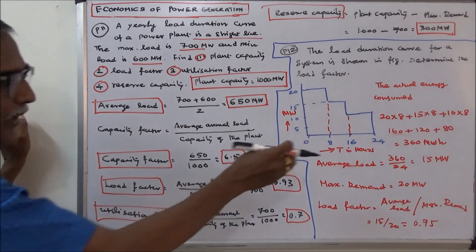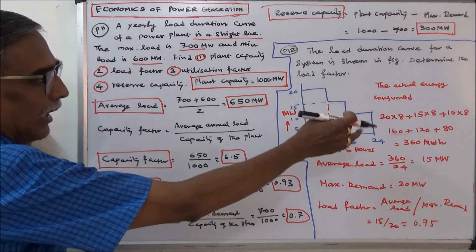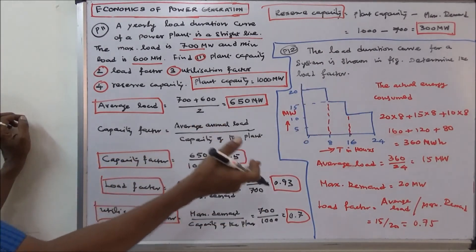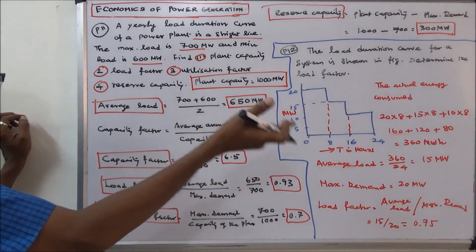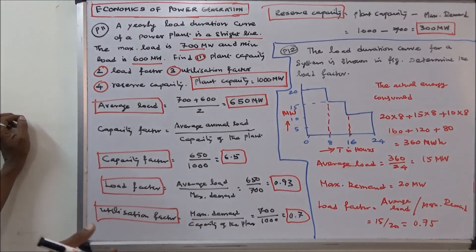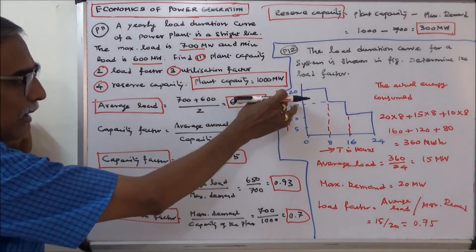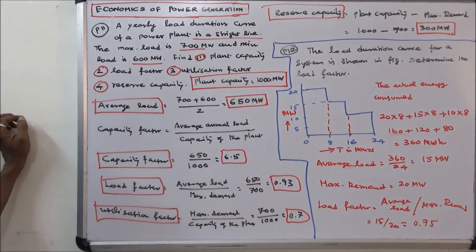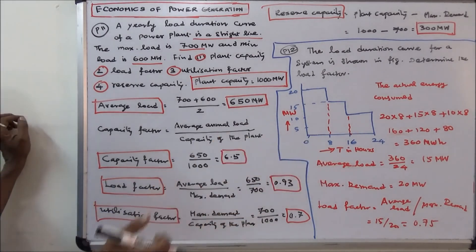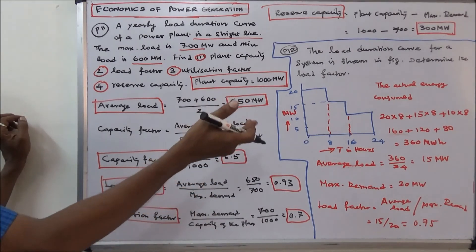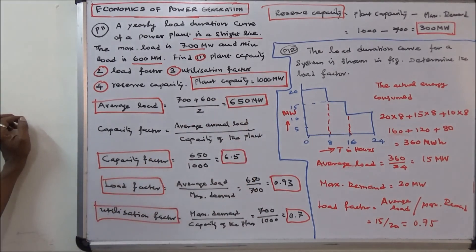The average load equals energy consumed in a day divided by 24: 360 divided by 24 equals 15 megawatts. The maximum demand is 20 megawatts. Load factor equals average load divided by maximum demand: 15 divided by 20 equals 0.75.